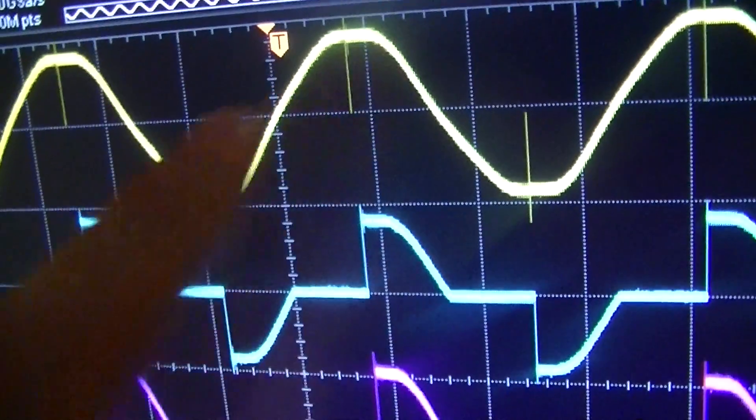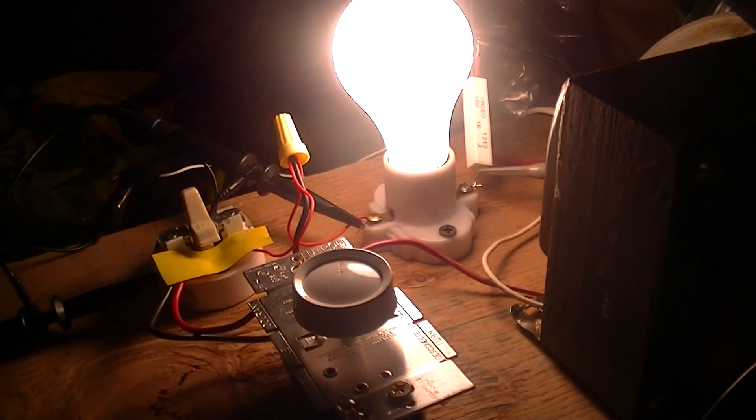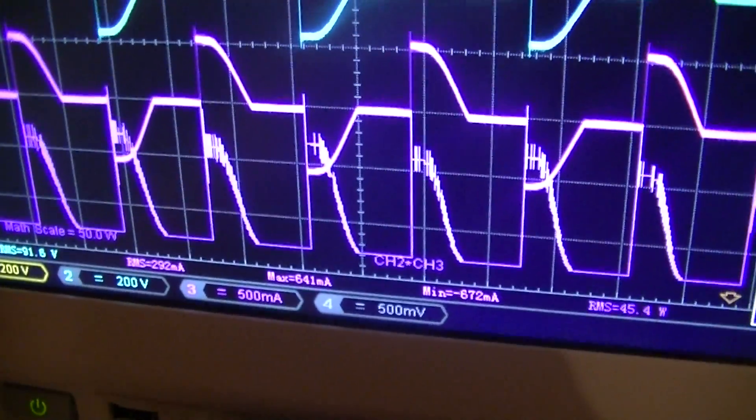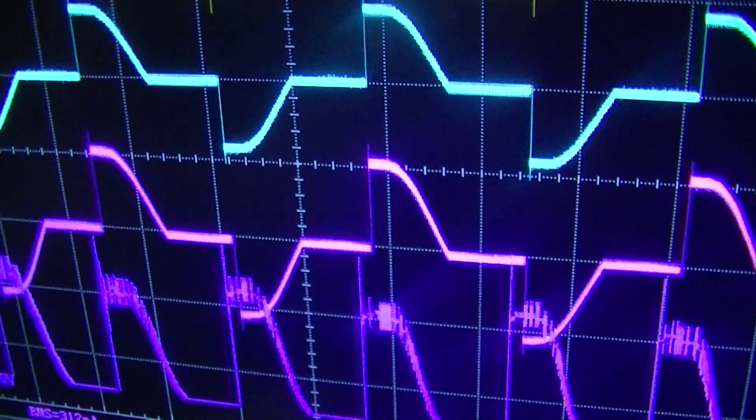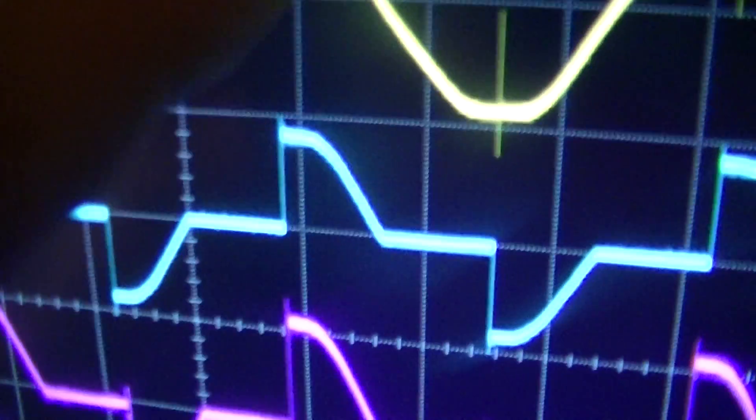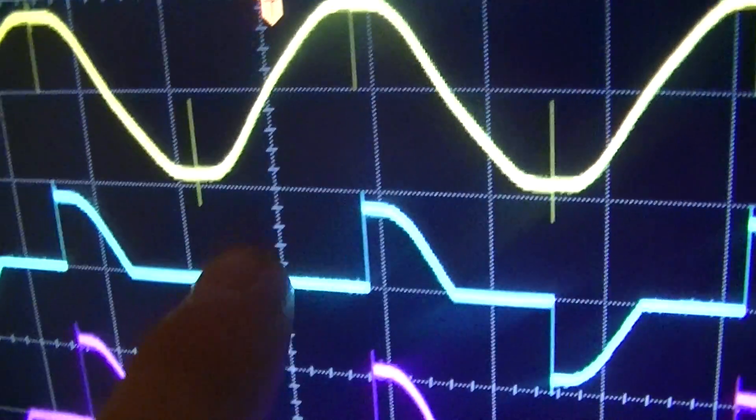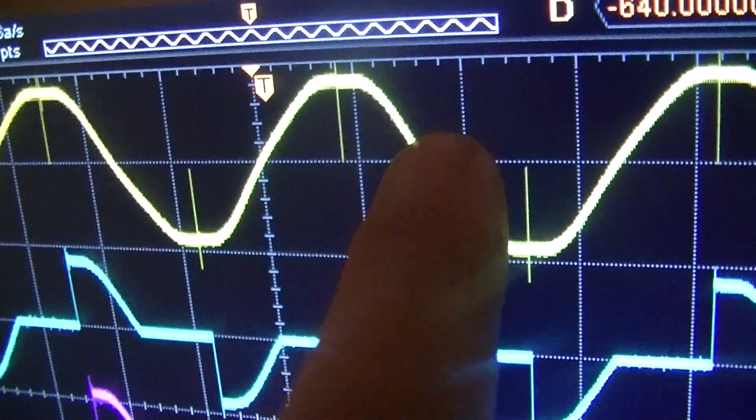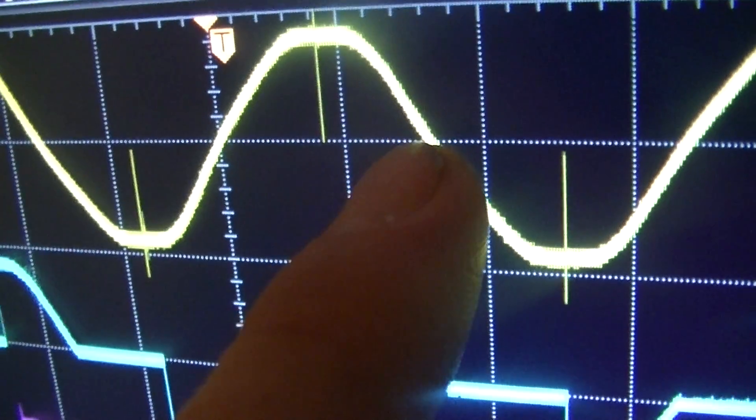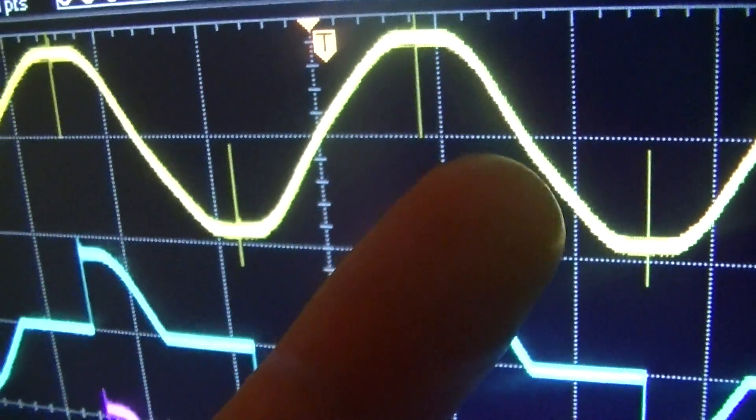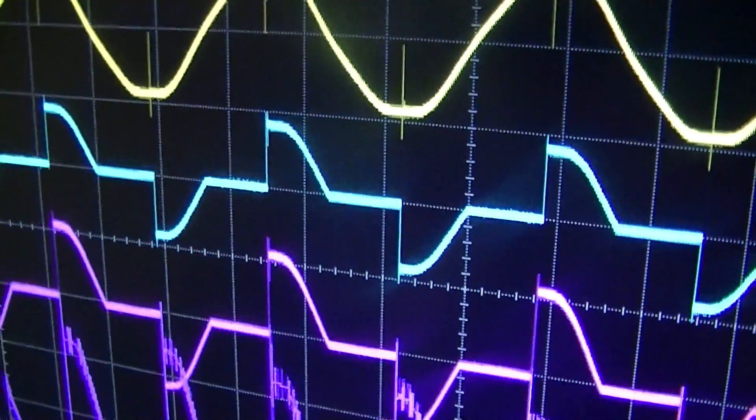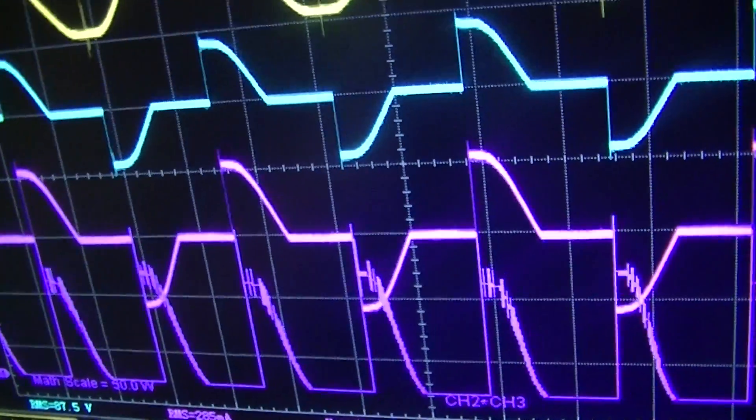And of course, also that peak current is being introduced onto the mains right at the peak of the waveform, because most people are going to dim lamps about halfway-ish, as I am doing right now. And that is one of the reasons why the mains supply, nowadays, it's very common to see it flat-topped. And another thing that you'll notice is that because of all this current being drawn in latter halves of each half-wave cycle, in the latter part of each half cycle, but not in the front, you can see that the decay of the potential down to, of the mains supply down to zero cross is a lot steeper than when it's rising from zero cross up to peak. And a lot of that has to do with the many hundreds of millions of dimmers on the grid. And the many, many gigawatts of lamps dimmed in such a manner.